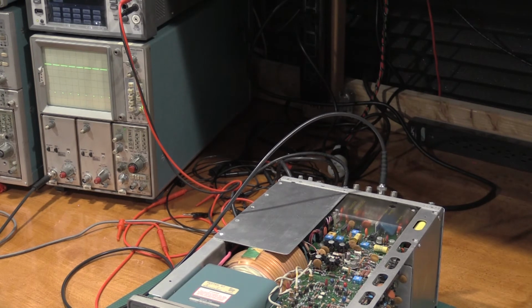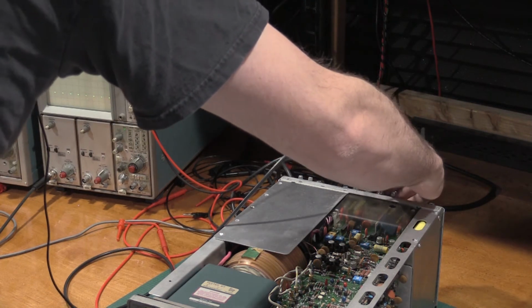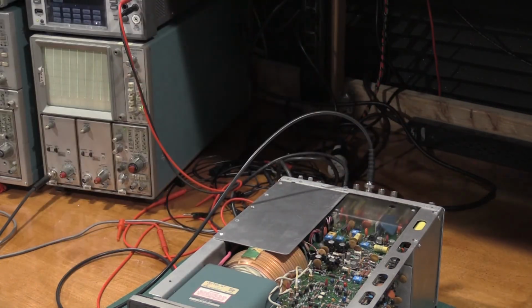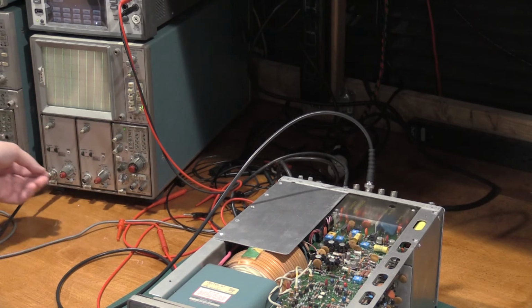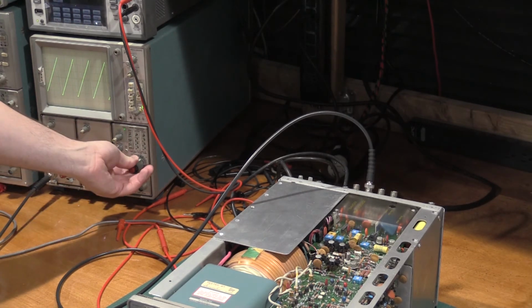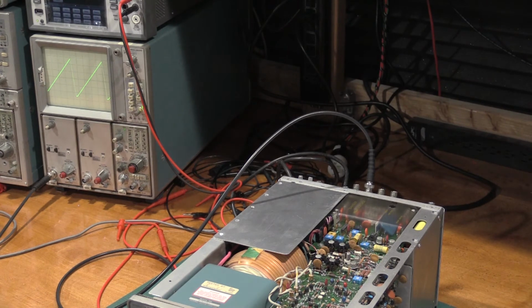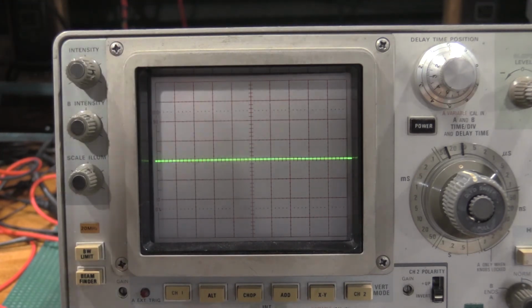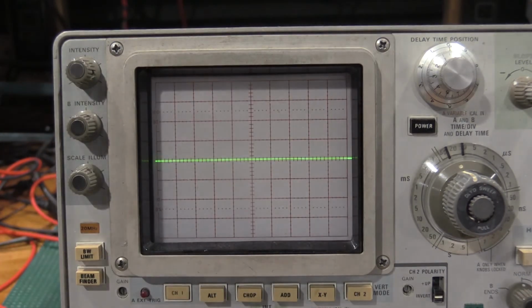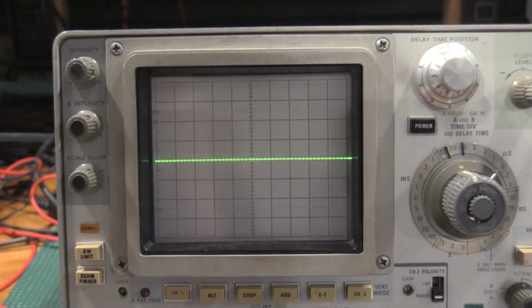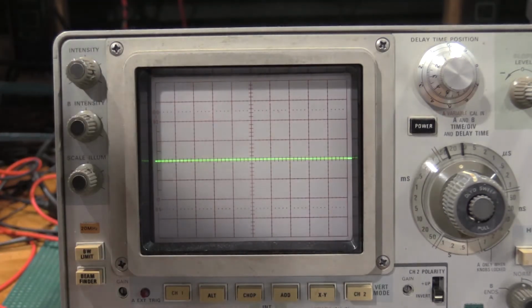The B sweep is working. So I have A gating and B gating. And then we should have a sweep. Yep. We have an A sweep sawtooth. So that is all our external sources working. We know focus and astig is working. And we should be good, so we're up to trace rotation. To be perfectly honest, looking at that, trace rotation is good, so I'm not even going to mess with it. Trace rotation's on the back corner where the outputs are, but in this case, it is good.